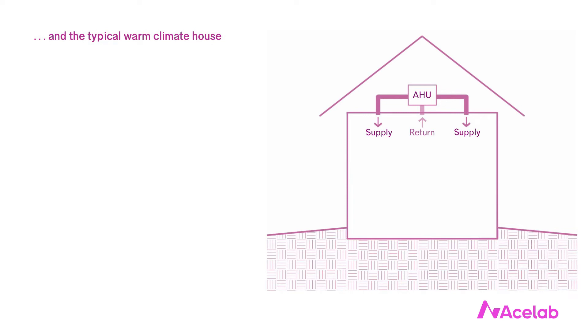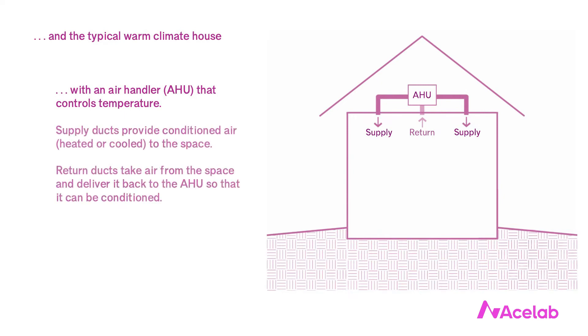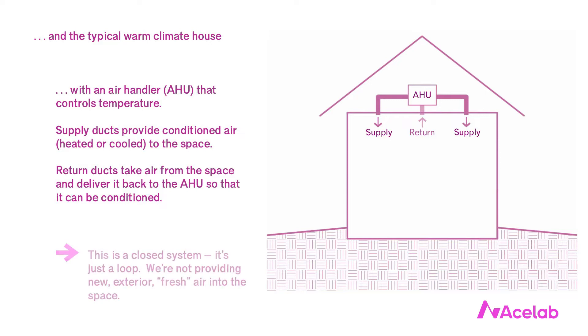Let's look at a single story warm climate house. We've got a similar setup: an air handler that controls temperature, supply ducts providing conditioned air to the space, and return ducts taking air back to the air handler to be conditioned. Just like our cold climate house, it's a closed system. One important difference though — the warm climate house has the air handler and the distribution system, the ducts, outside of the thermal enclosure. They're in the attic, which is usually vented, so they're effectively outside.